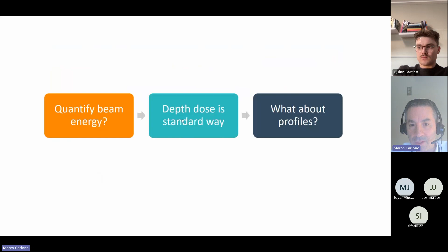So they looked at profiles. This is two figures out of the paper, and I'm going to reproduce this in a second using our simulator. What they did is they configured a TrueBeam linear accelerator for different beam energies, by changing the bending magnet current, which changes the beam energy, and this changes the profile of the FFF beam. They showed quite nicely that you can get very different profiles, which you can measure the differences between, and these are more sensitive to beam energy changes than the depth dose changes, which is the normal way of doing this.